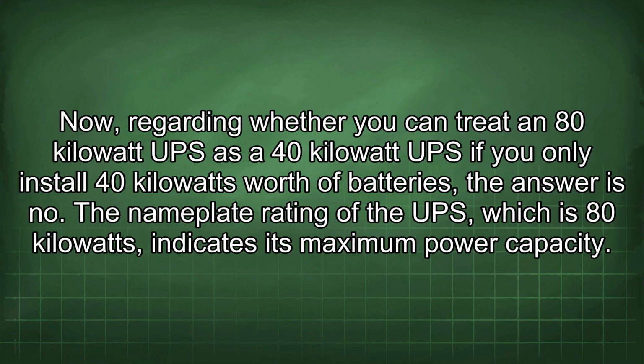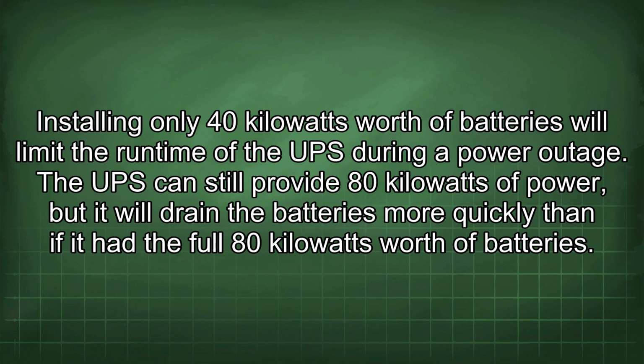Now, regarding whether you can treat an 80 kilowatt UPS as a 40 kilowatt UPS if you only install 40 kilowatts worth of batteries, the answer is no. The nameplate rating of the UPS, which is 80 kilowatts, indicates its maximum power capacity. Installing only 40 kilowatts worth of batteries will limit the runtime of the UPS during a power outage. The UPS can still provide 80 kilowatts of power, but it will drain the batteries more quickly than if it had the full 80 kilowatts worth of batteries.